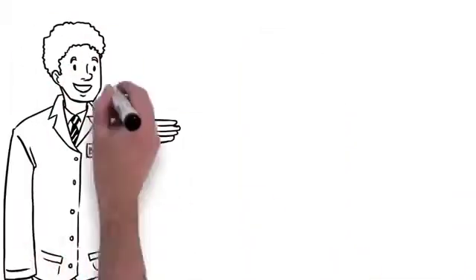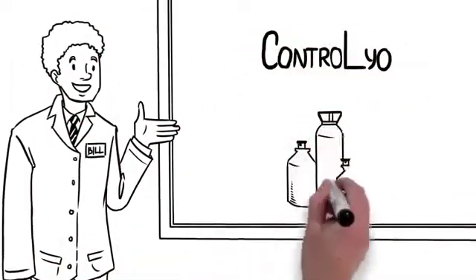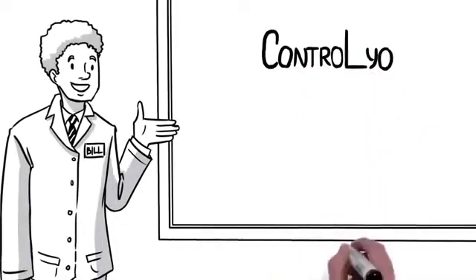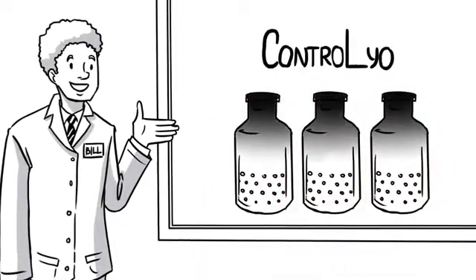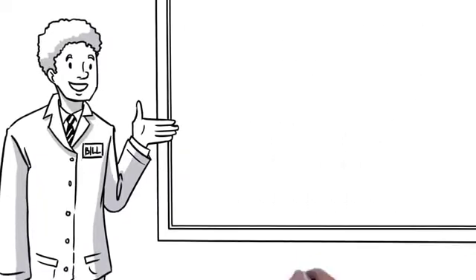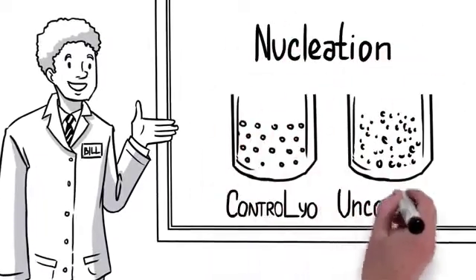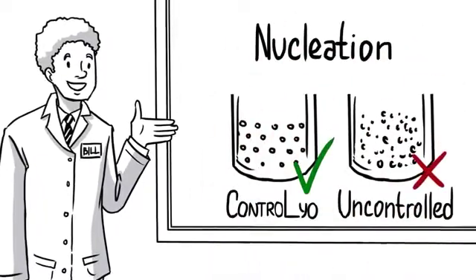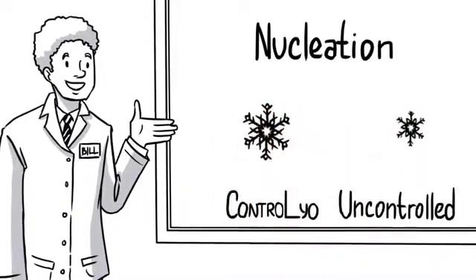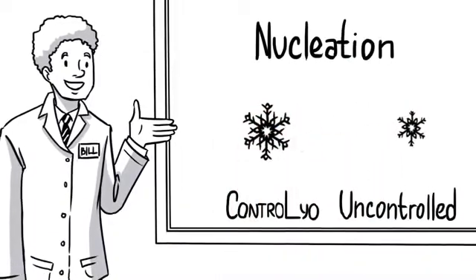Control-Lyo technology uses an inert gas to pressurize the freeze drying chamber. This results in complete freezing of all vials at the same time and reduced supercooling. Vials actually freeze at a higher temperature and yield larger, more consistent crystal sizes. These larger crystals allow faster sublimation due to less product resistance.